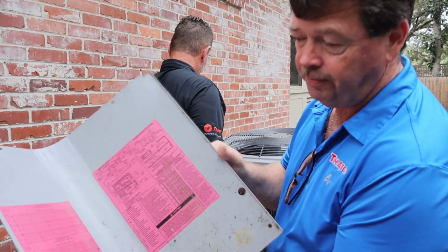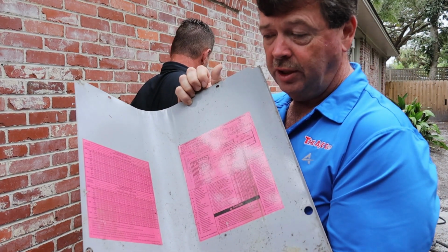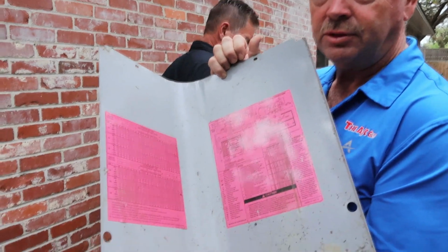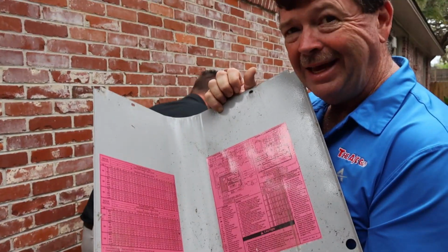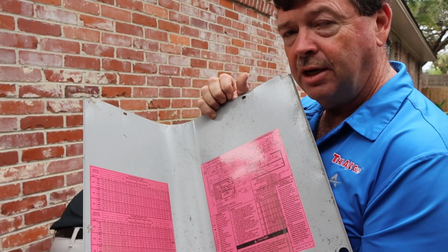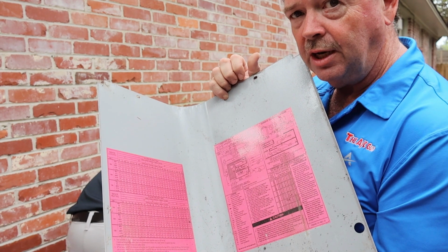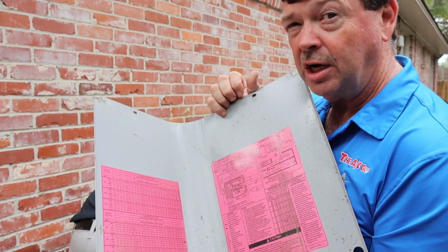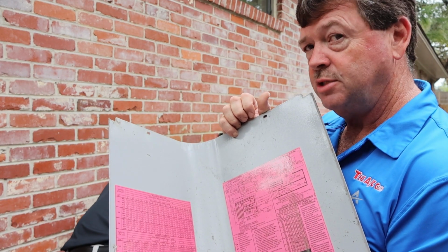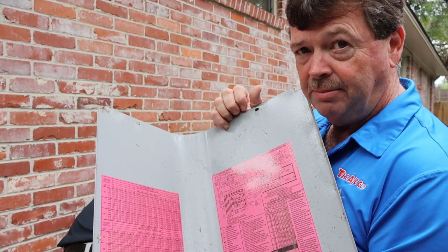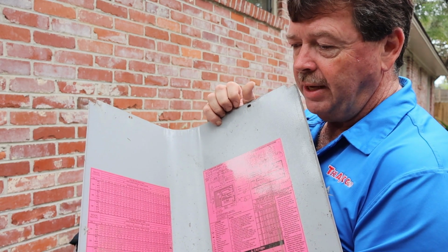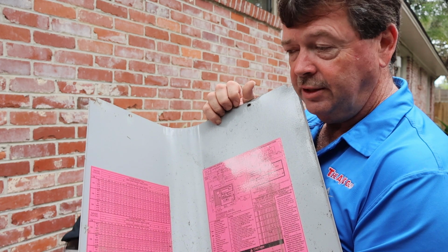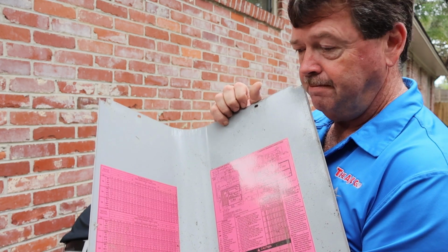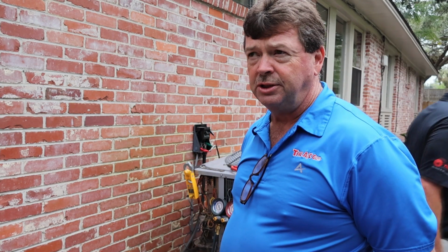Most manufacturers have charts that will help you to determine that the Freon levels are correct or not. There's parameters in which these Freon pressures should be at given outdoor conditions. So this helps a technician determine the Freon levels are where they should approximately be. So with these measurements that we're taking now, with this information that the manufacturer provides for us, it's going to make it a little easier for us to confirm that these Freon pressures are right where they need to be. We've currently determined our Freon charge is correct.